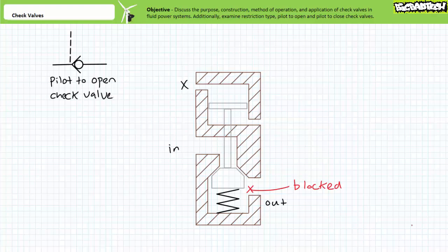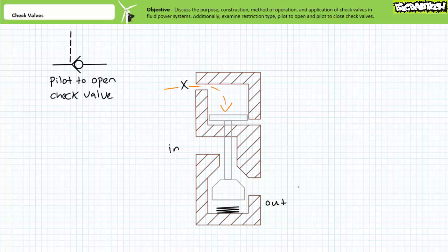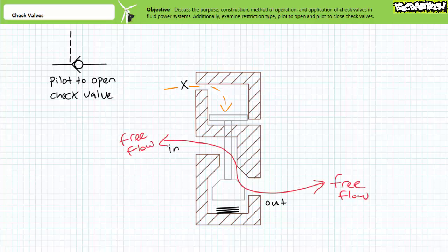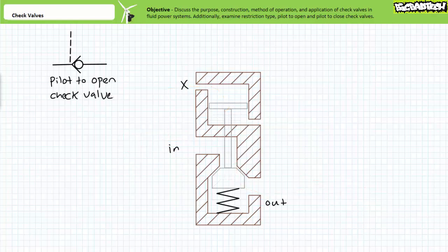In the blocked position, the poppet is forced on the seat and fluid flow stops. This behavior radically changes however in the presence of a pilot signal. As the name pilot to open implies, when pilot pressure pushes on the piston face, the connecting rod pushes open the poppet and fluid can now pass in both directions unimpeded. When the pilot pressure signal disappears, the bias spring forces the poppet onto the seat and normal check valve behavior resumes.